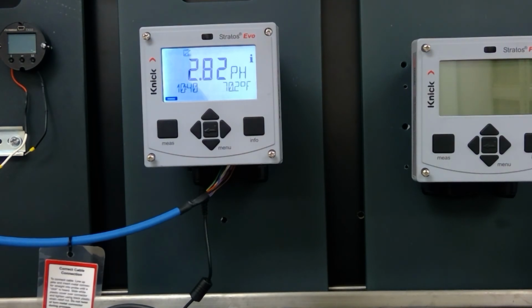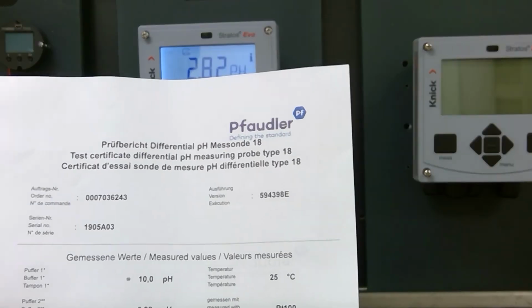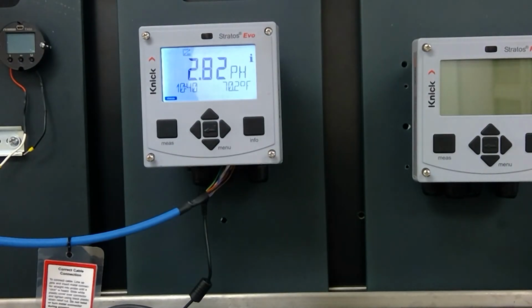So just wanted to make sure that when you go do this configuration, you have the calibration or test certificate, you have everything wired up, and you hydrate the sensor for calibration. Of course, you need to make sure that you have the TAN code for Pfaudler. When you purchase the transmitter, it should already have that TAN code, but if for some reason it didn't, you would have the ability by contacting us to put that TAN code in to make it compatible with the Pfaudler sensor. So I hope this information has been valuable.